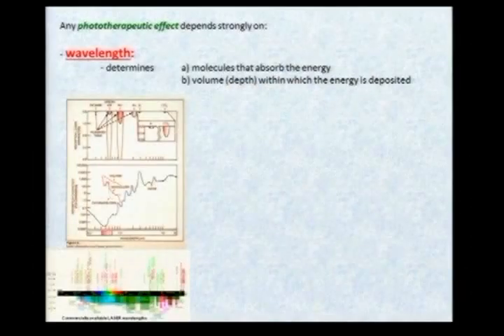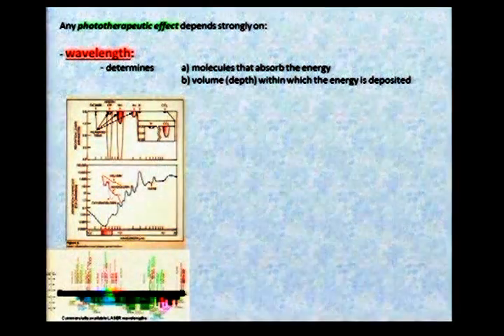There are two parameters that determine precision and selectivity. The first is wavelength, because it determines two things: the molecules that absorb the energy, and the depth into which the energy is deposited. If you want to close down blood vessels, you have to use a wavelength absorbed by hemoglobin. This slide shows the spectrum of tissue components — hemoglobin and water — on a logarithmic scale, along with the 1/e penetration depth of light at different wavelengths, varying from several millimeters to a fraction of a millimeter.